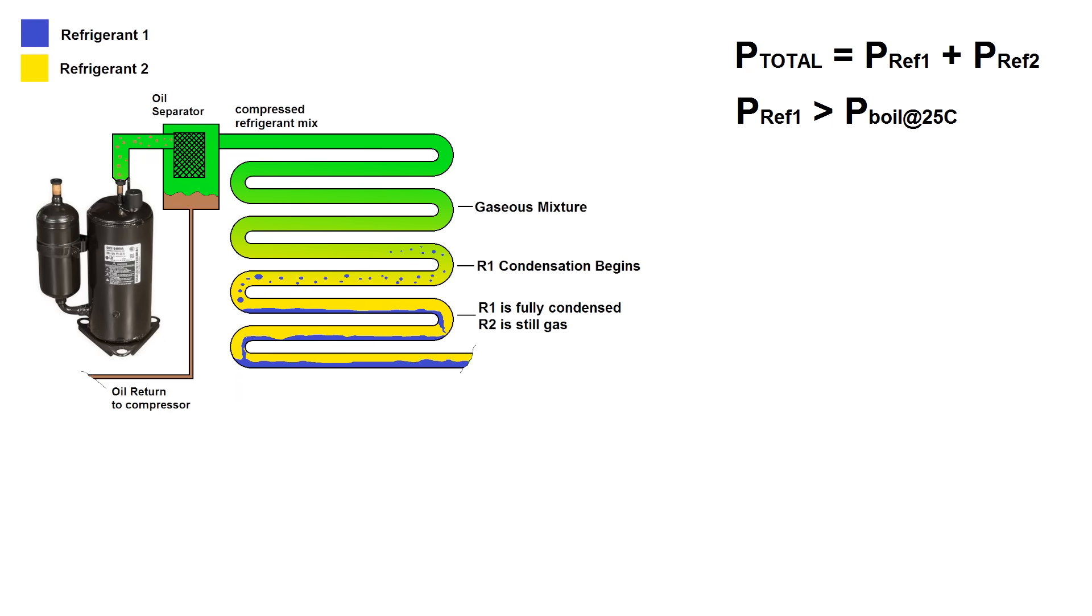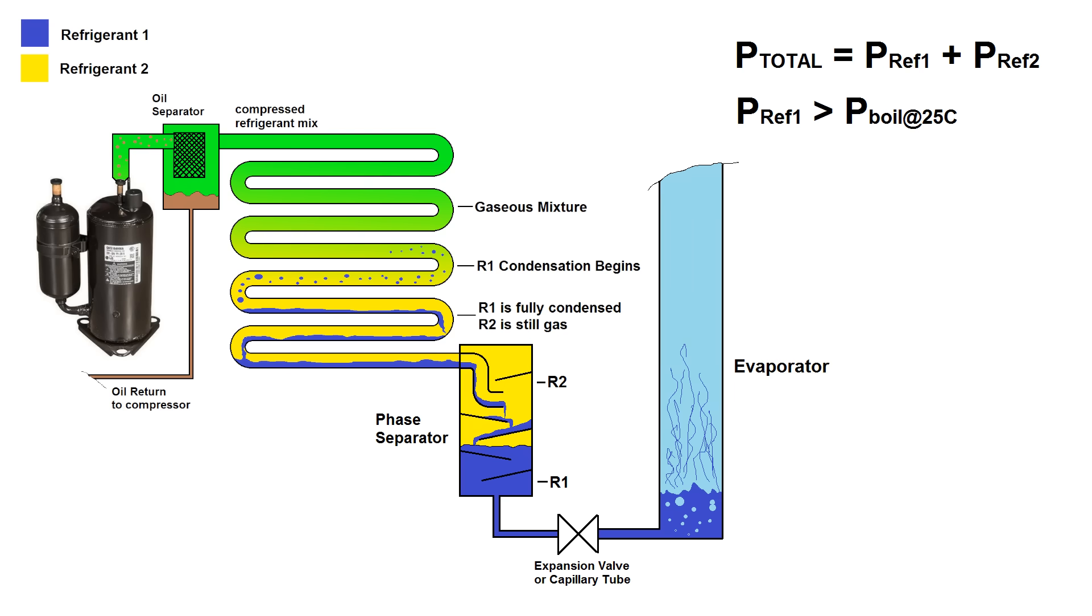Now here's where things get interesting. The gas liquid mixture flows into a chamber called a phase separator that uses gravity and some baffles to separate the gas from the liquid by letting the liquid fall to the bottom and the gas rise to the top. Since the first refrigerant has already condensed to liquid, but the second refrigerant is still gas, this pretty much completely separates the two refrigerants. The liquefied refrigerant one goes into an expansion valve or capillary tube. Its pressure drops, it boils in an evaporator, then returns to the compressor inlet, just like with a regular vapor compression system.